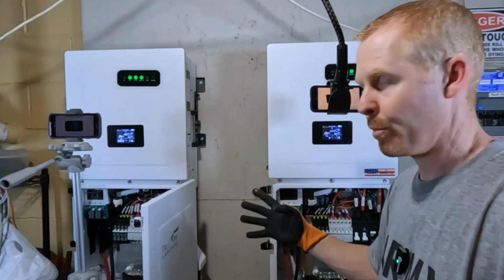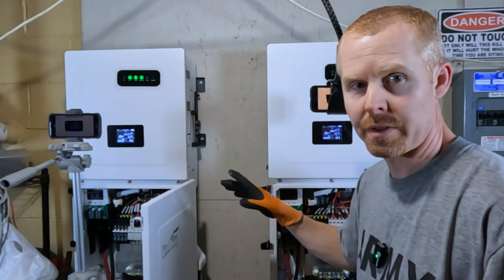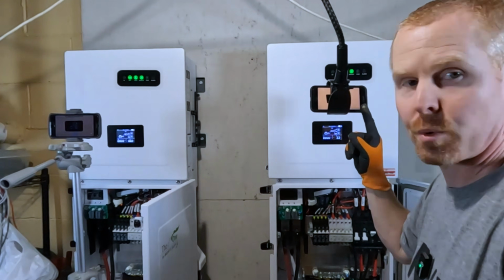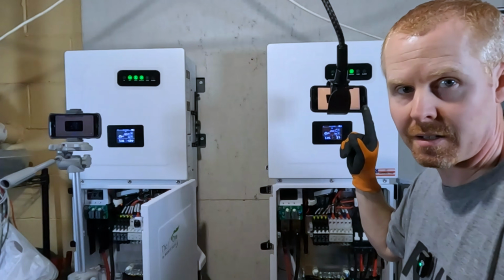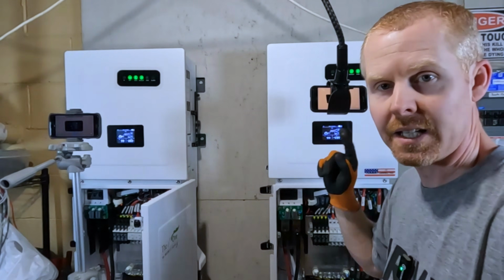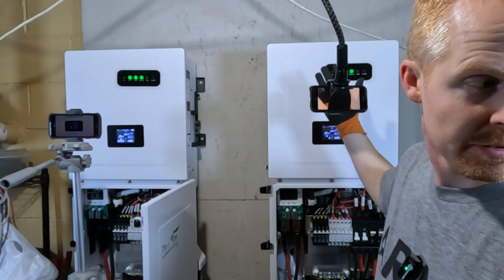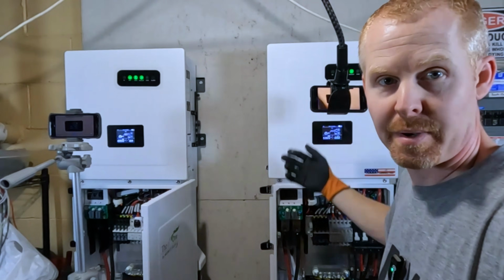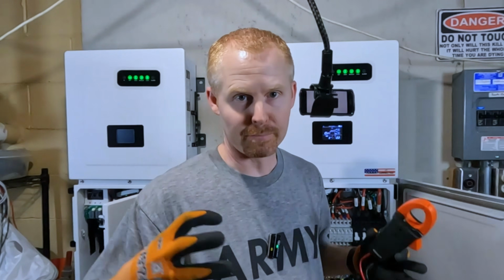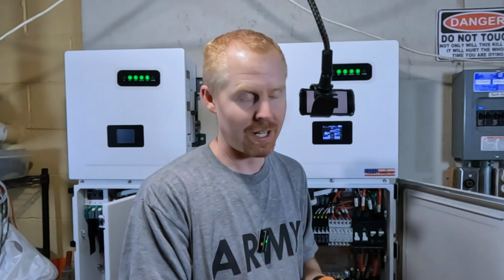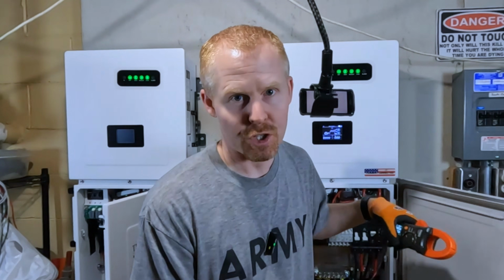So we still have the output turned off on both inverters. I've got the screen recording still going on one inverter—I believe it's the master. Yep, it's the master. So before I flip that switch and merge the two inverters' outputs together, let's check voltages just to make sure, sanity check.